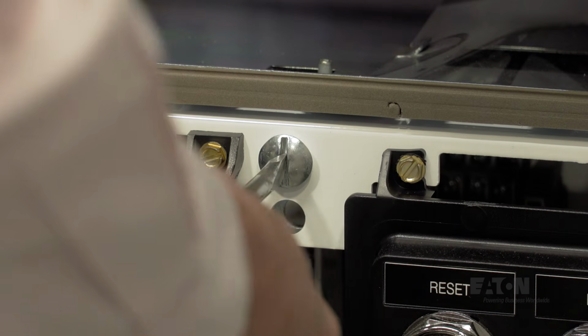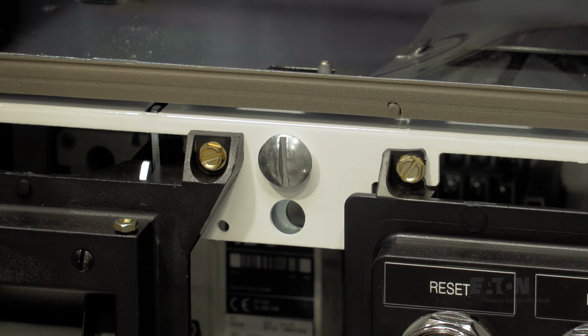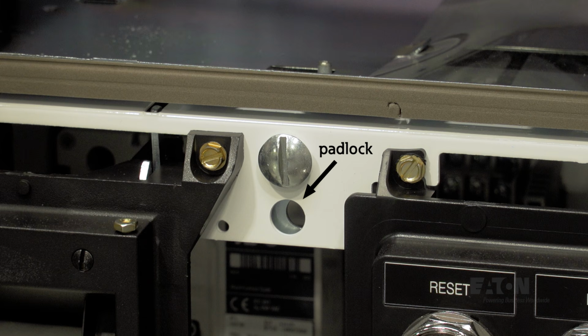Upon release of the latch, the unit can be partially withdrawn such that the stabs disengage from the vertical bus. In this position, the latch can be re-engaged to prevent the unit from being returned to the fully stabbed position or from being removed from the structure. The latch can be padlocked in this position to ensure that the stabs remain disengaged during maintenance.